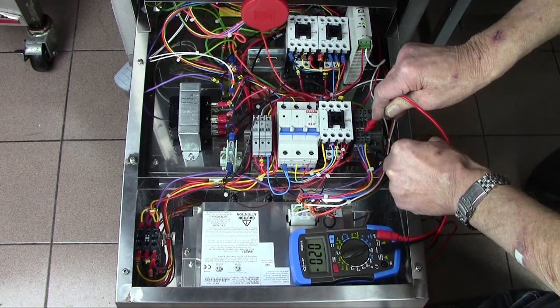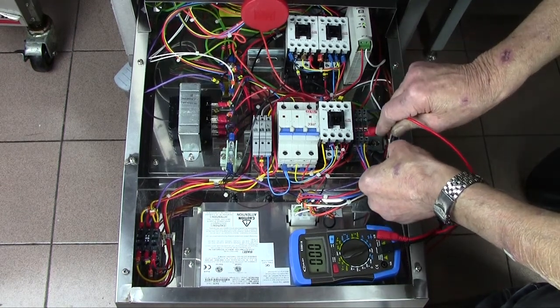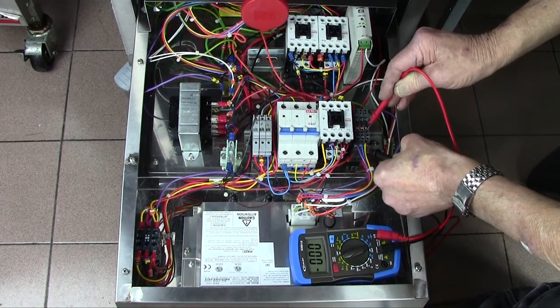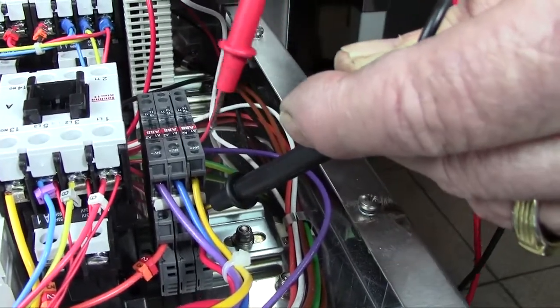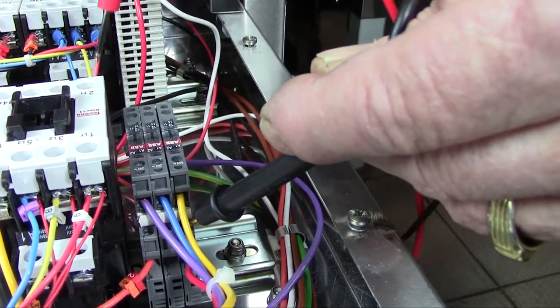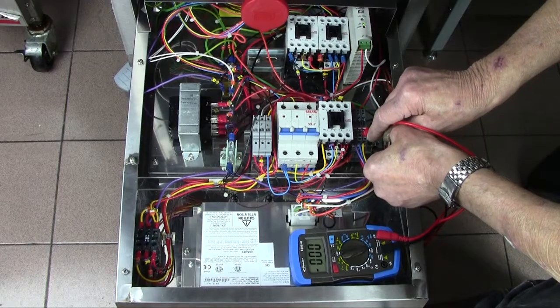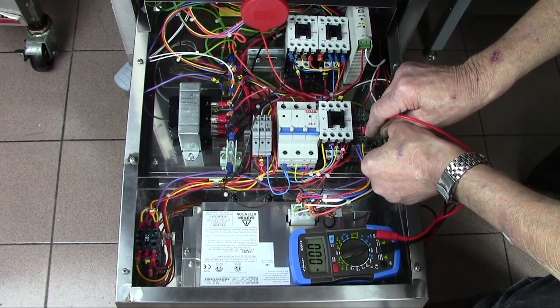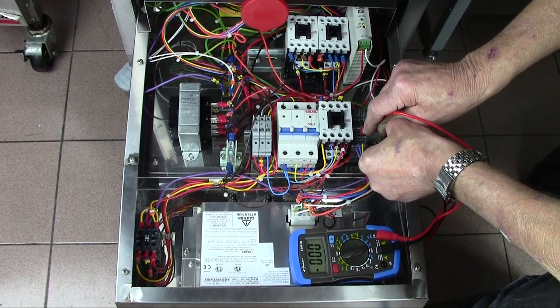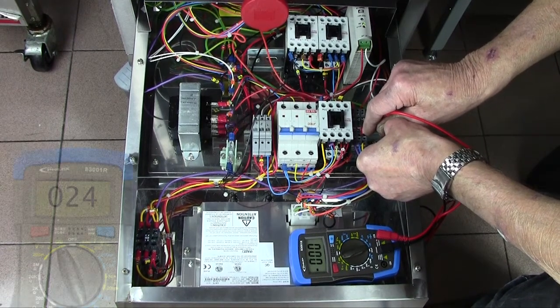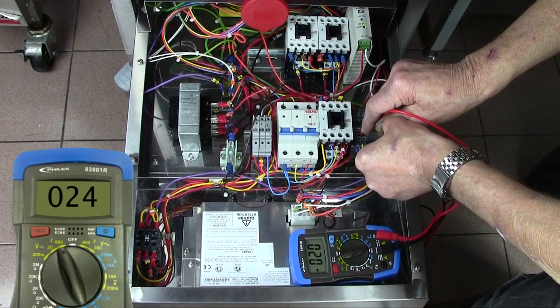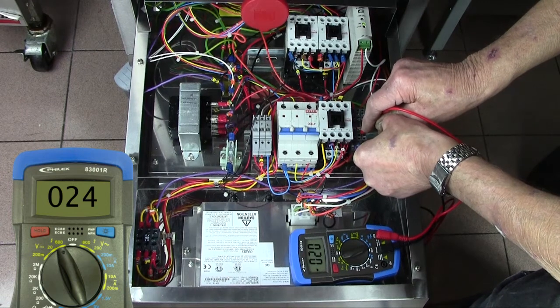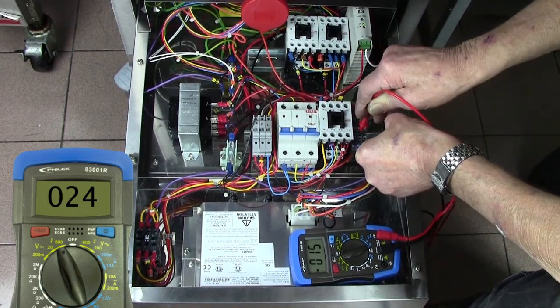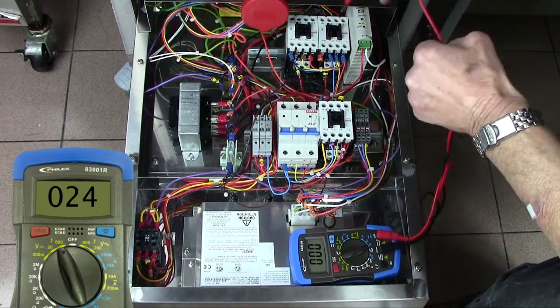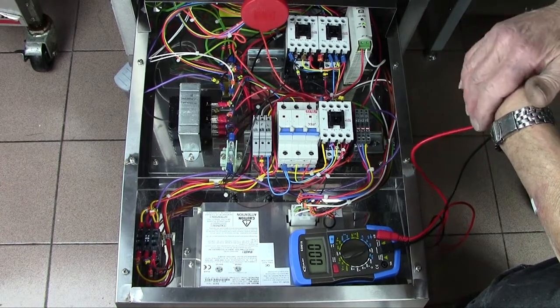To check the relays, go on to the lower screws that are all bridged together. The top one, the middle one at the top, is the coil for that relay. Unfortunately it pulses, so you have to wait for the pulse to come back on, and when the pulse comes on, check that you're getting the correct voltage to there. If the voltage doesn't exist, it'll be a fault from the board or a fault from the high limit. It's on, it's showing 20 volts, and at the same time as that goes on, over here the contactor will pull in at the same time as the relay pulls in.